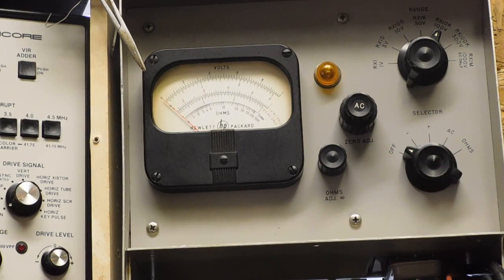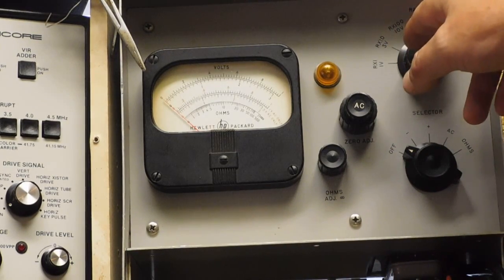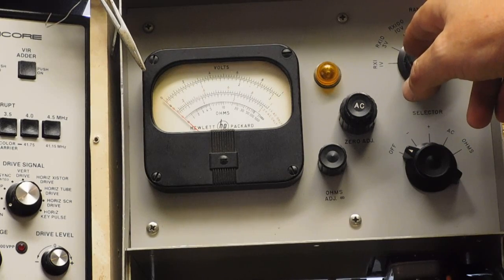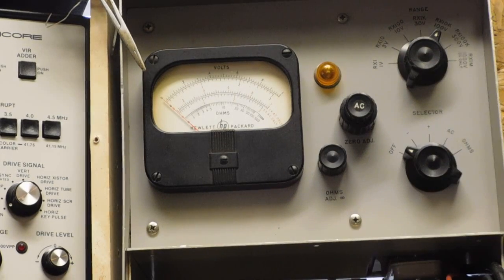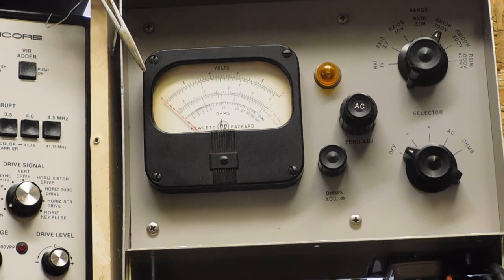This is 122 megohms. The other thing is AC actually uses a special probe. We'll look at it, it came with it, but it's a rectifier. It has a rectifier diode tube in it, and it's high frequency. Basically it has a flat level on the curve from DC all the way through 500 megahertz.